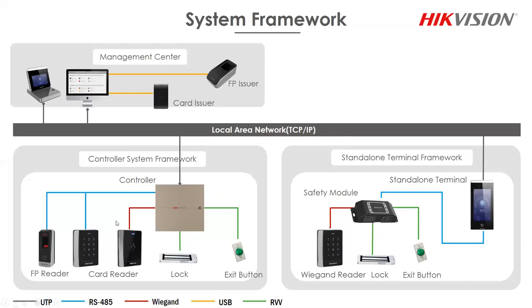Our controller is an IP-based controller, so it connects to the network, and we have software to centrally manage the controller. All permissions are downloaded from the software through the network to the controller, and the controller saves all the permissions. Once a card is presented at a card reader, the card number is uploaded to the controller, which checks its database to verify authorization. If authorized, the controller talks to the lock and opens the door.